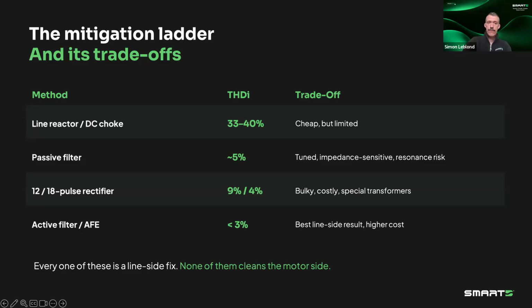And then we come to active front end drives or active filters, which will typically get you the best harmonic performance. We'll talk about them in a second, but I'll just highlight here that none of these harmonic solutions actually address the motor side. So they're really just a line side solution.